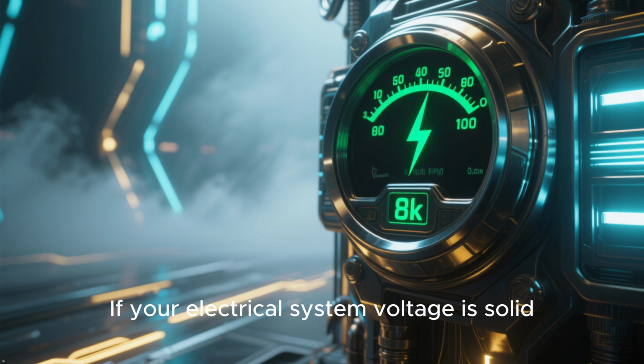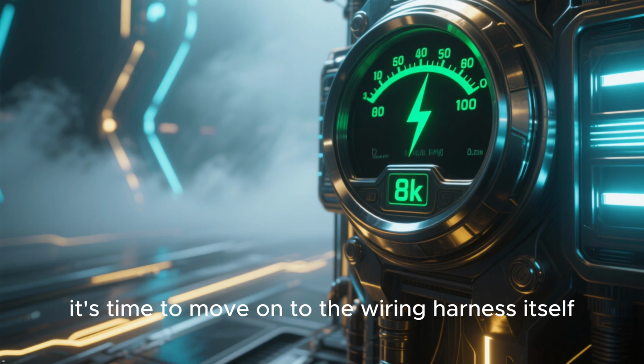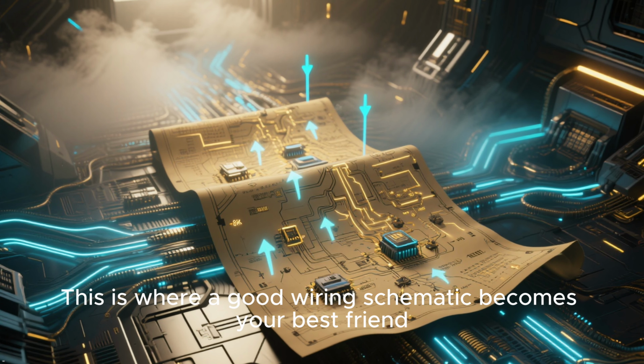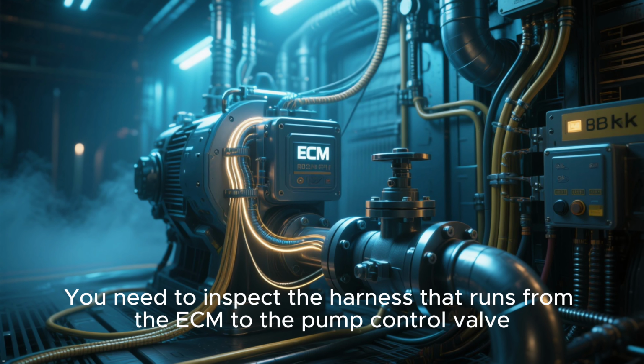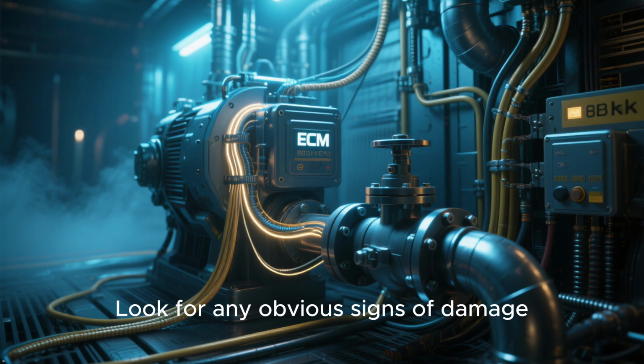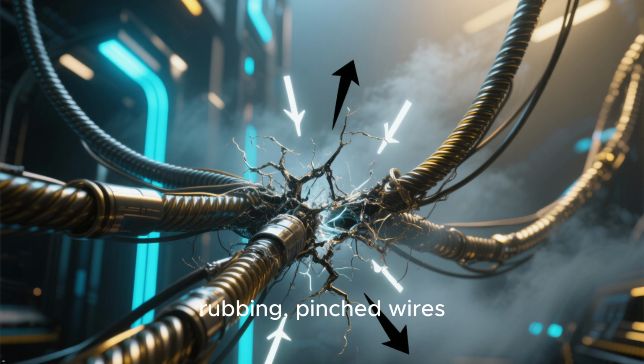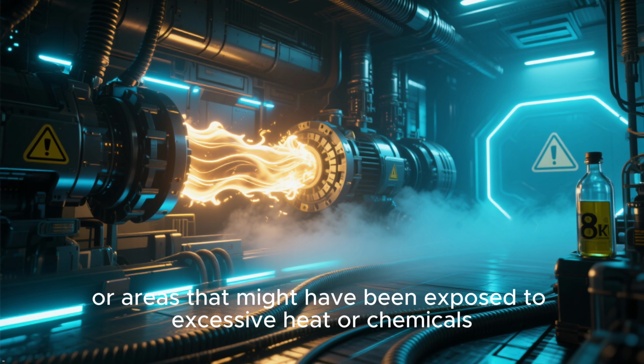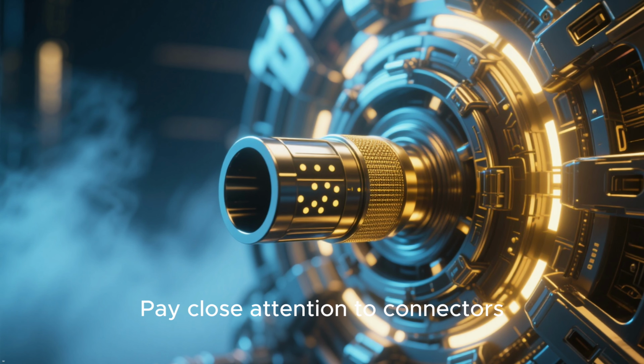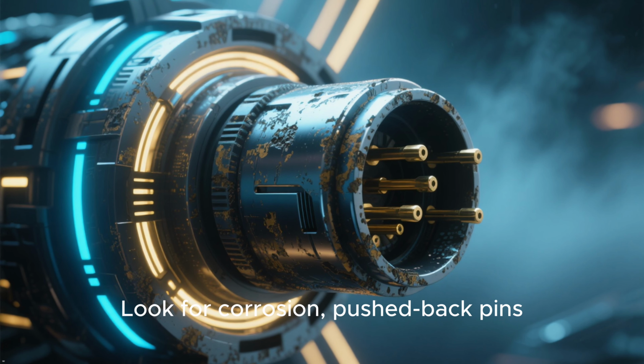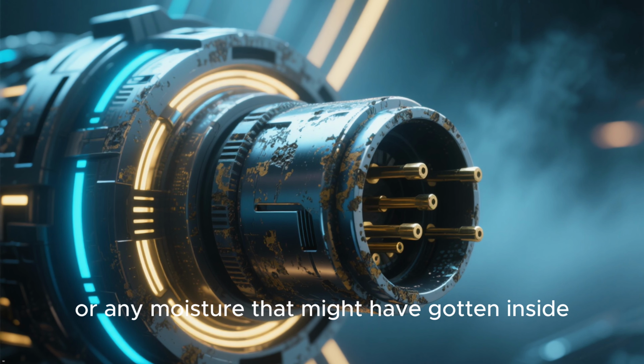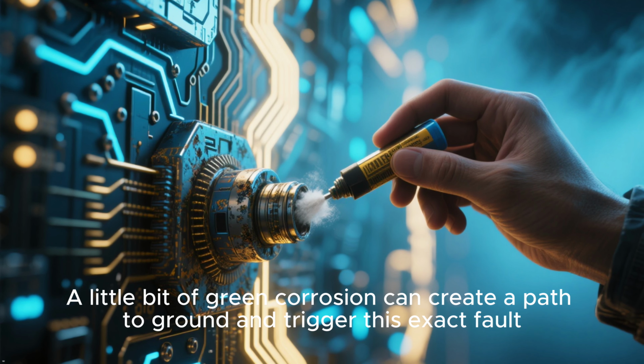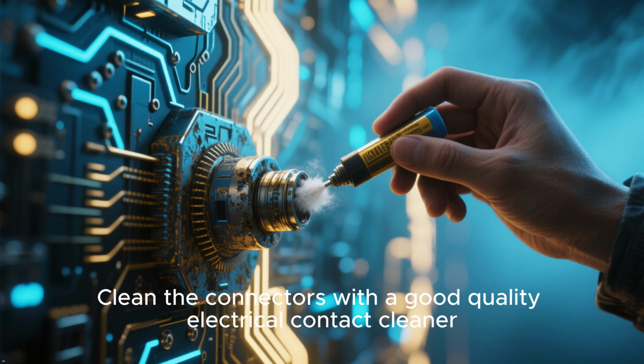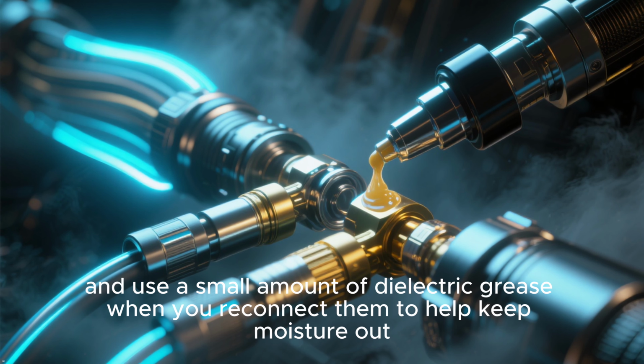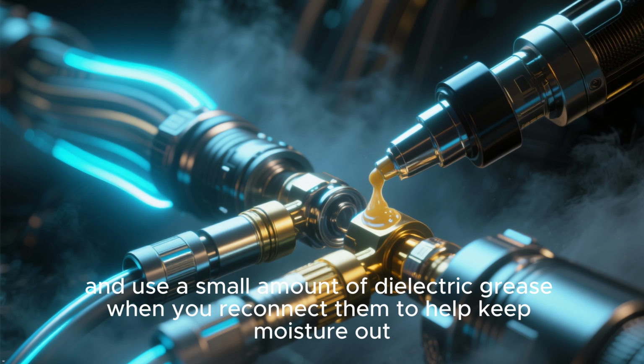If your electrical system voltage is solid, it's time to move on to the wiring harness itself. This is where a good wiring schematic becomes your best friend. You need to inspect the harness that runs from the ECM to the pump control valve. Look for any obvious signs of damage. We're talking about chafing, rubbing, pinched wires, or areas that might have been exposed to excessive heat or chemicals. Pay close attention to connectors. Unplug the connector at the valve and the one at the ECM. Look for corrosion, pushback pins, or any moisture that might have gotten inside. A little bit of green corrosion can create a path to ground and trigger this exact fault. Clean the connectors with a good quality electrical contact cleaner, and use a small amount of dielectric grease when you reconnect them to help keep moisture out.